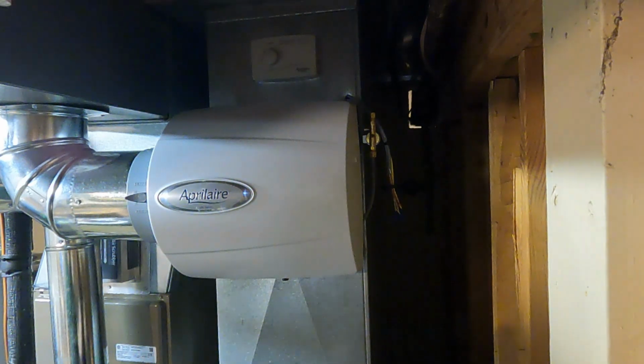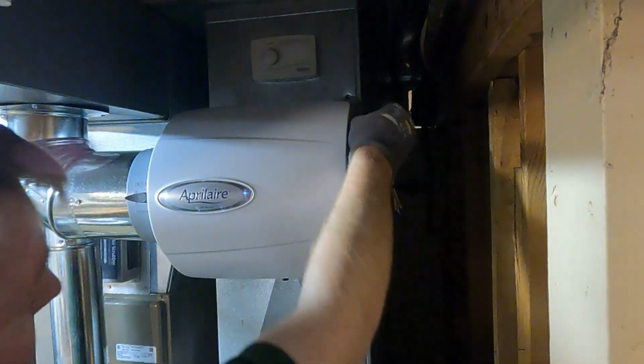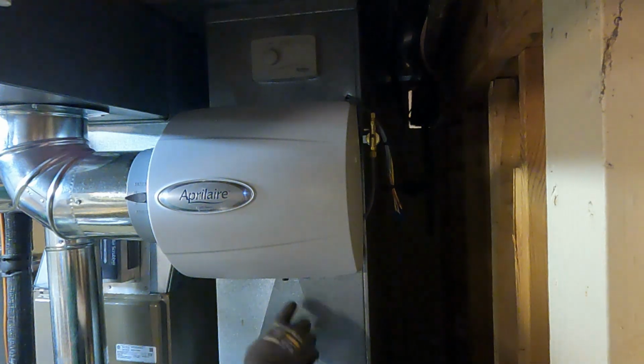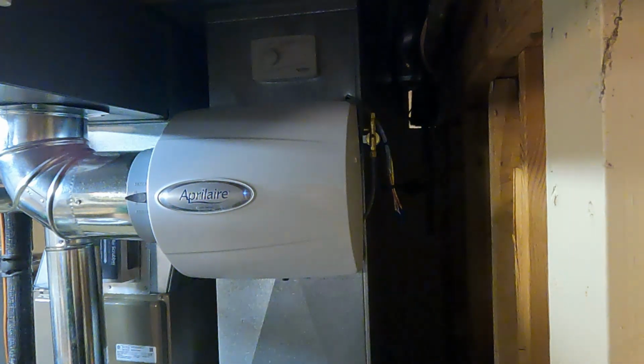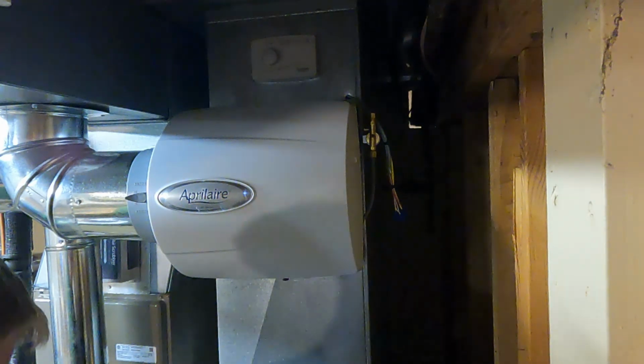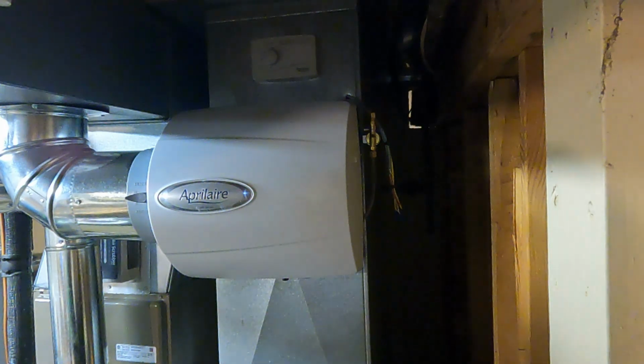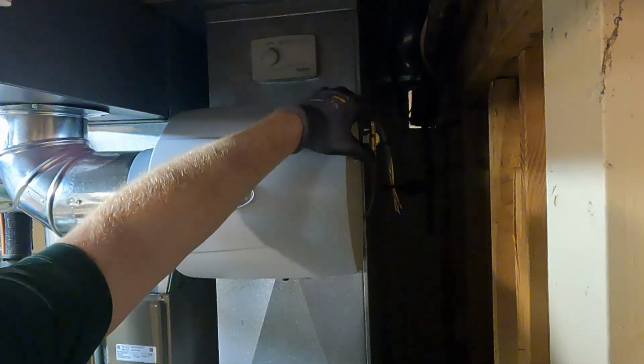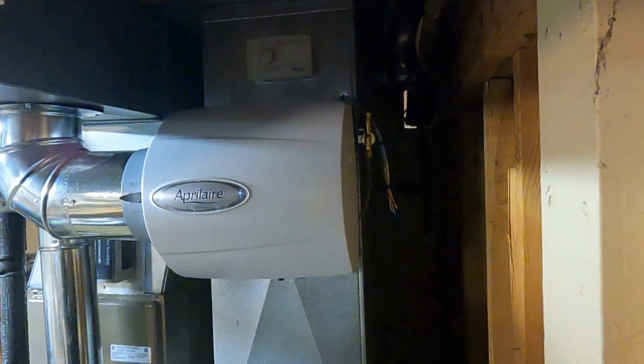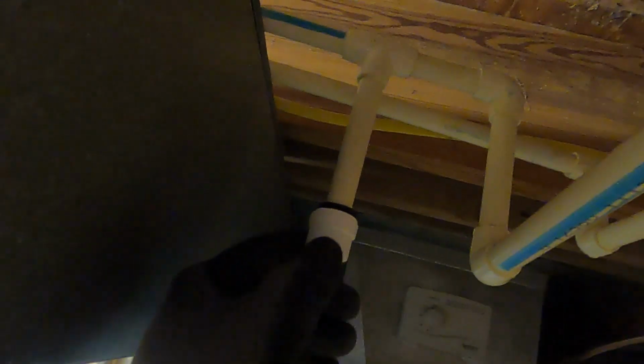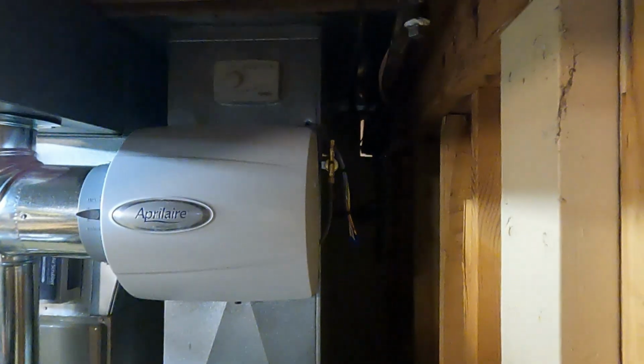Alright, all that is left now is tying in the water line, the water supply, and the drain. So the customer already has a condensate pump over here, so I'm just going to route this drain in condensate tubing, run it down along the top of the furnace, make it look all nice. And then what we're going to have to do is tap into the hot water line. As you can see, there used to be a water heater sitting right here. So I'm actually going to tee into it right up here with the fitting and come across with a nice little braided hose going right over the top of it. So we will get started on that.